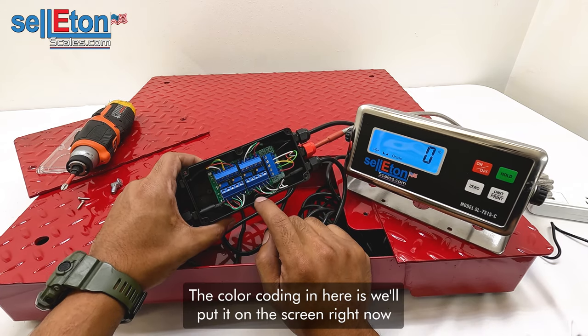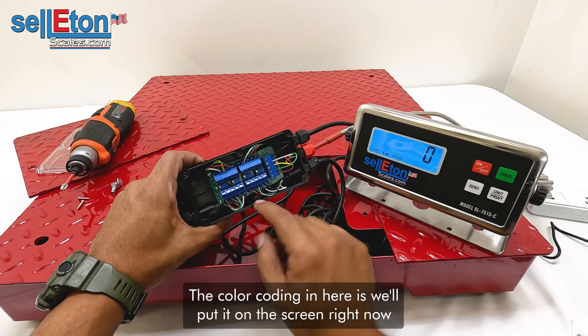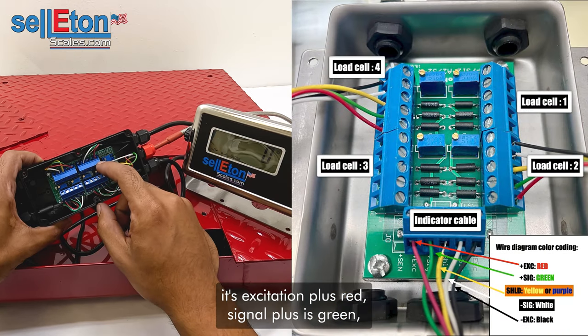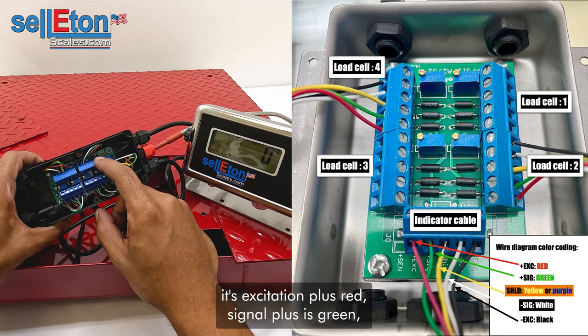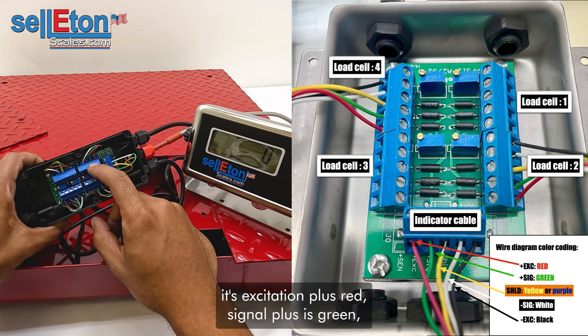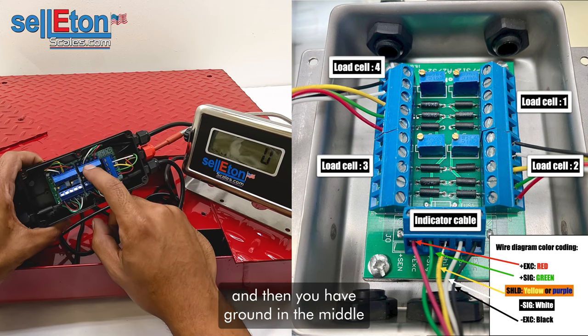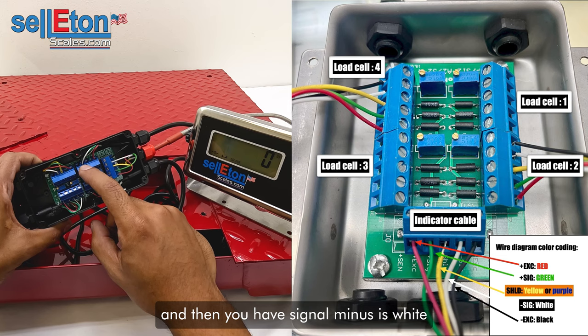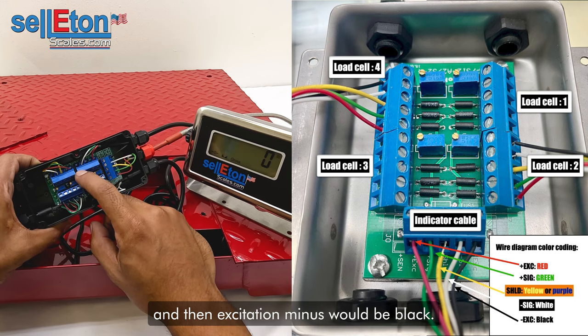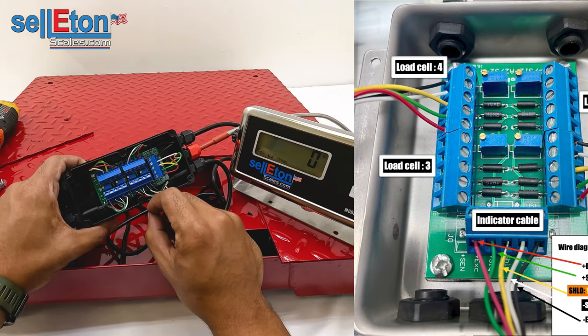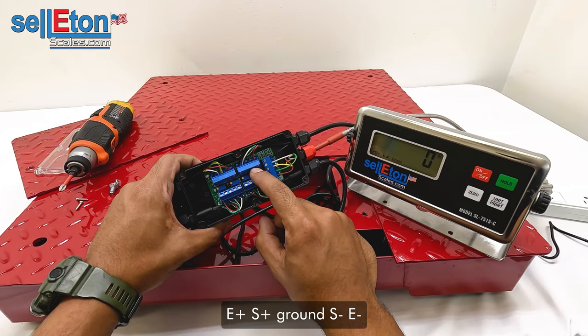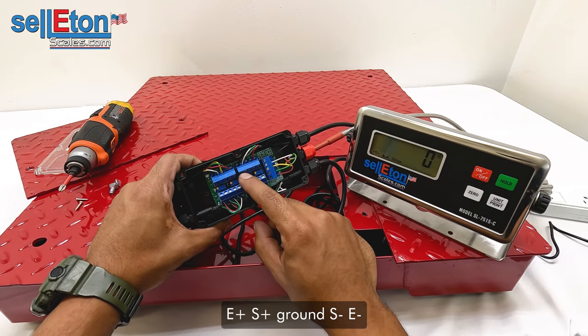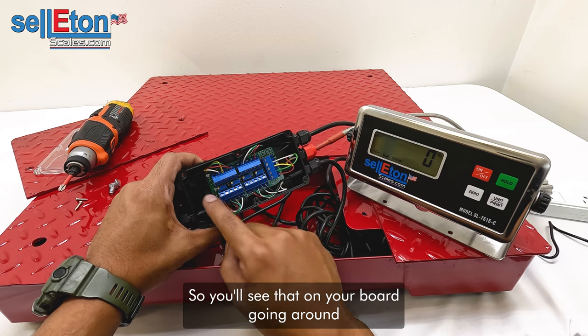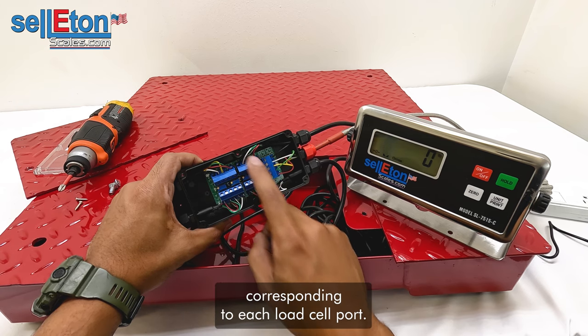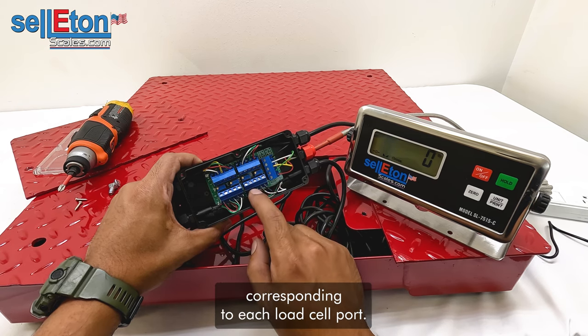The color coding in here is, we'll put it on the screen right now. It's excitation plus red, signal plus is green, and then you have ground in the middle, and then signal minus is white, and then excitation minus would be black. That's usually E plus, S plus, ground, S minus, E minus. So you'll see that on your board going around corresponding to each load cell port.